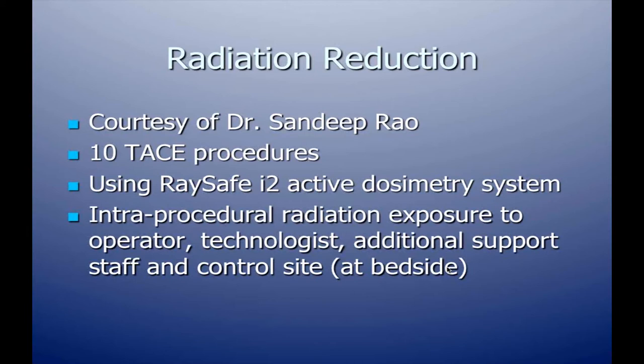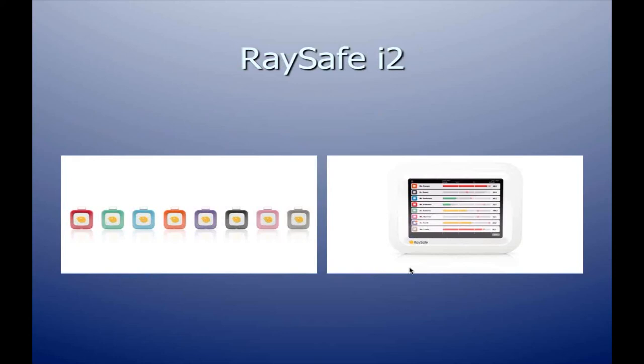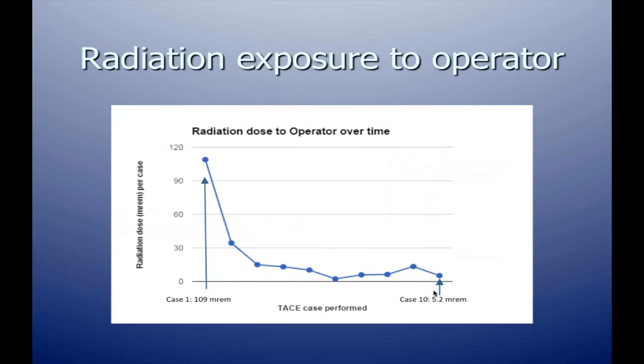On the important issue of radiation reduction: this data is courtesy of Dr. Sandeep Rao in El Paso, Texas, who performed 10 TACE procedures and used the RaySafe I2 active dosimetry system to measure intra-procedural radiation exposure to the operator, technologist, additional support staff, and at the table-side control. The dosimeters provide direct real-time feedback during the procedure. Radiation dose to the operator significantly decreased over time — for the last seven cases worked from the independent workstation, the physician's radiation dose was markedly reduced.